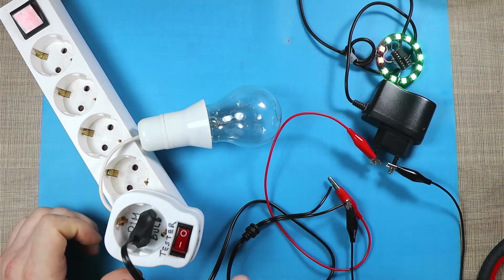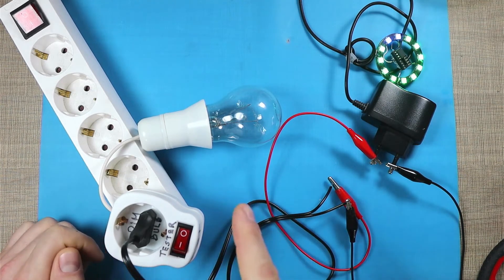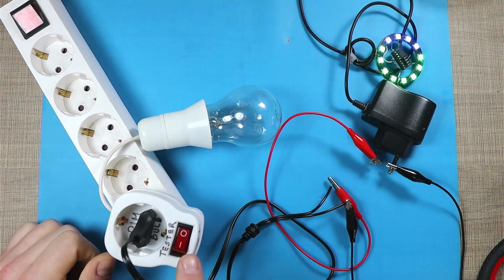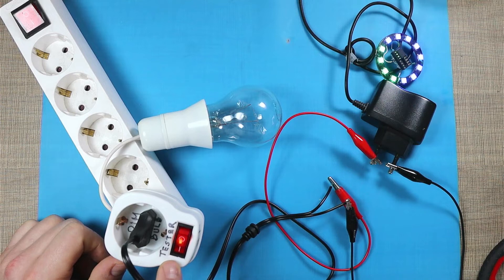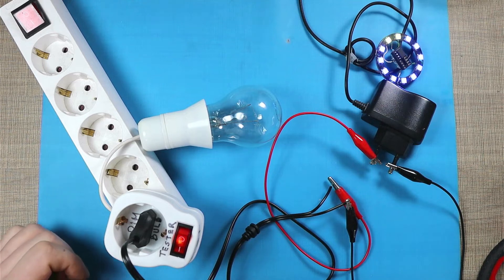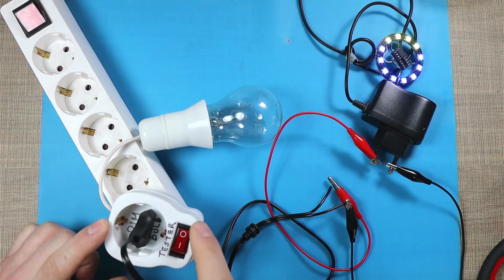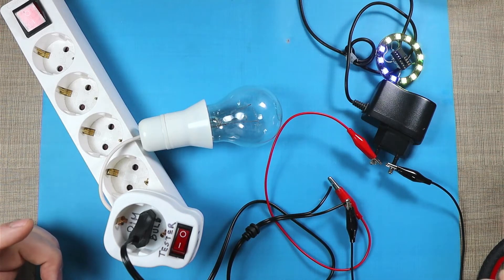The important thing here to note is that because this switch will short out the bulb, if we have the switch in the on position, if the light here lights up, then any short in the device will actually cause an explosion. So be aware of that and always use the tester with the light bulb in line.